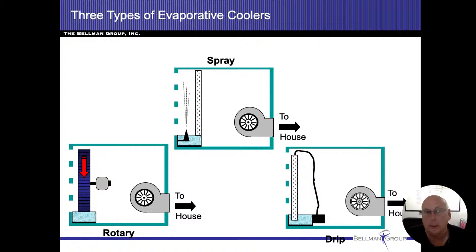So it's hard for us Northerners to understand this, but in this case, these evaporative coolers run with high flow air, big ductwork. You actually keep your windows open when you're doing this. You blow the humidity in the house. That moisture evaporates because of the very dry climate that they live in. And as it evaporates, it absorbs the heat of all the objects in the house, including the human beings that it touches. And they actually work fantastic. Everybody that has them says that they're marvelous.